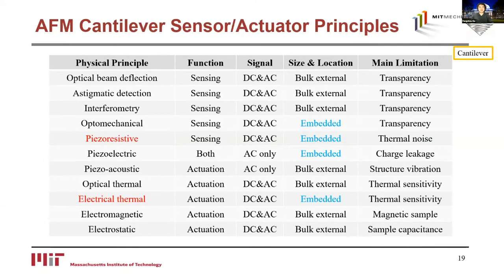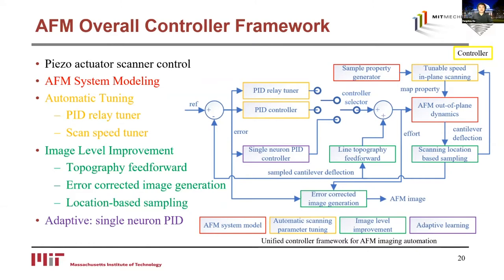Now let's take a look at the general framework of our controller, the third key aspect we'll be focusing on today. This slide shows an overall framework of the color-coded AFM control system with automation and additional algorithms developed in this work. The fundamental-level control is the piezo-actuator scanner. The overall AFM dynamics are relatively complicated, but we can approximately model the AFM system and sample dynamics. Based on this model, we developed algorithms for automated PID relay-based tuning and in-plane scan speed tuning, as well as three image-level improvement algorithms: topography feed-forward, error-corrected image generation, and location-based sampling for increased-speed scanning. An adaptive single-neuron PID controller was also developed for cases with significant sample material property variation.